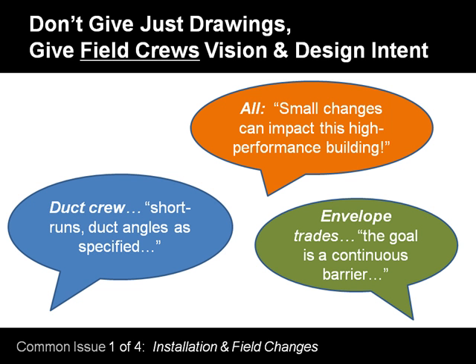So I think in talking about this previously, the recommendation had really been to get as close as you can to those field crews and have the design intent clear. So forget the drawings for a minute. Here's what we're trying to do with resistance. If you're talking to the duct crew, we're trying to have minimal resistance. Here's why the elbow sizes are so important. So again, it is that change in awareness, hopefully to reduce field changes. Maybe they'll be closer to the drawing. Correct. Similarly on the enclosure, we're trying to get a continuous membrane.